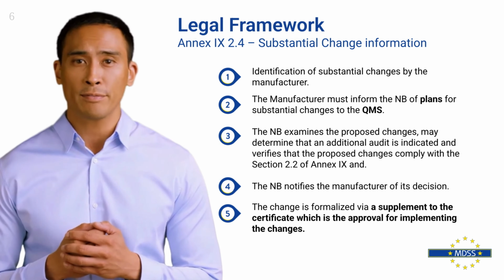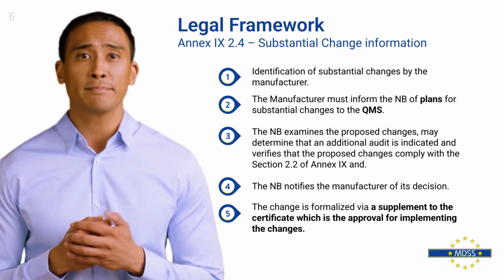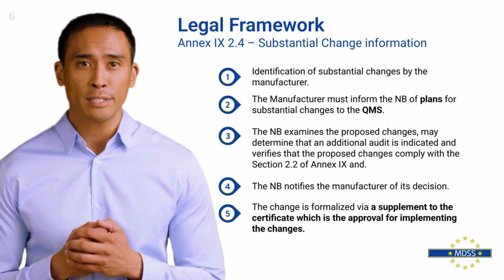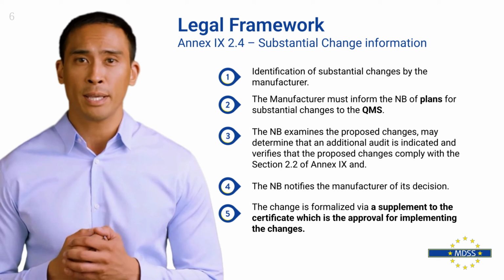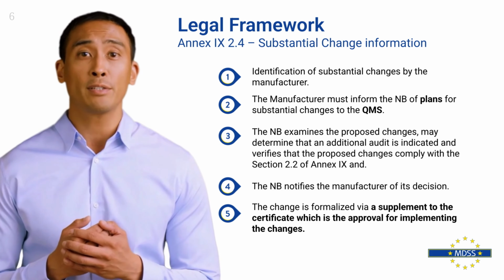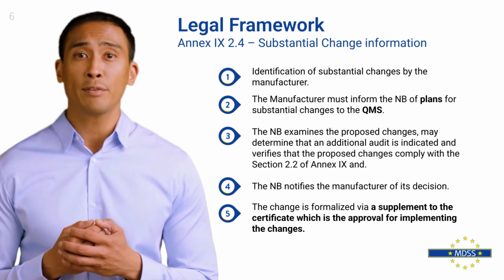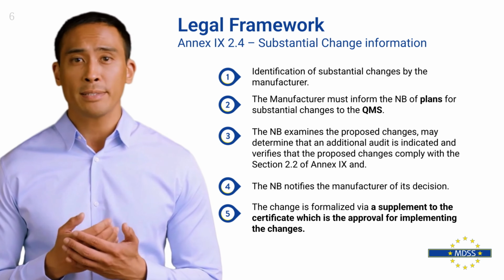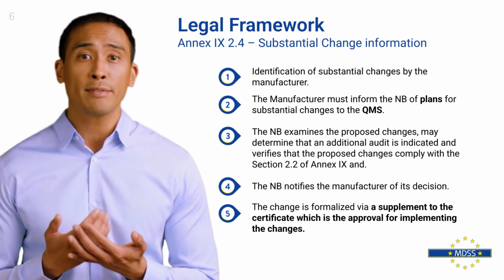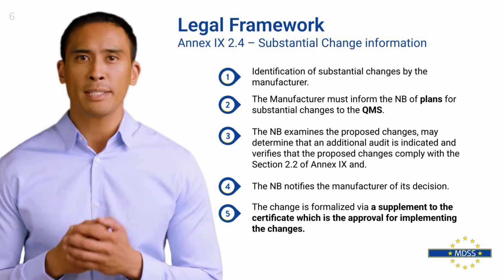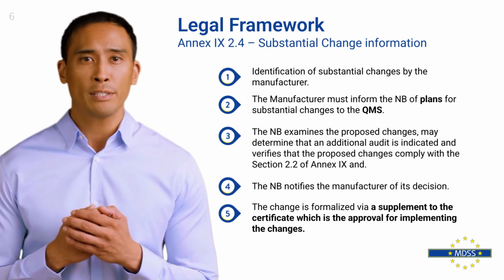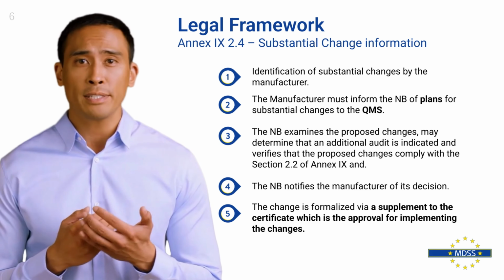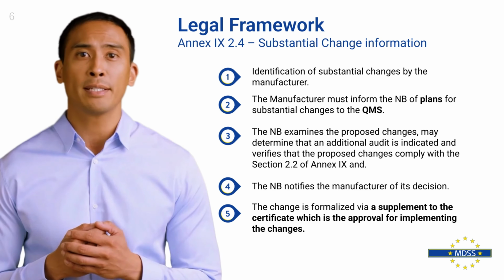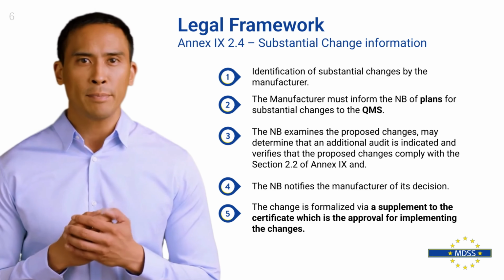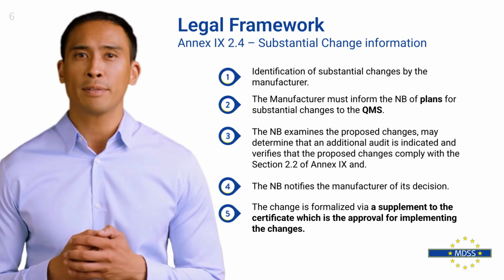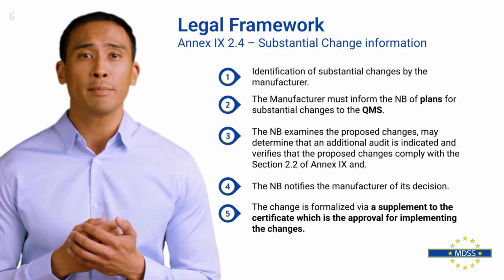Annex 9, Section 2.4 describes a process, not just a rule. This lays out a clear process regarding changes, particularly those that could substantially affect the quality management system. This is crucial. Again, the manufacturer is not required to inform the notified body of all changes to the quality management system. The notified body must only be informed of plans for substantial changes. If the intent of the regulation were to require notification of all changes, the MDR would have stated so explicitly. Once a plan for substantial change is identified and reported, the notified body must review the proposed change. This review, if deemed appropriate, results in an approval with a supplement to the certificate.